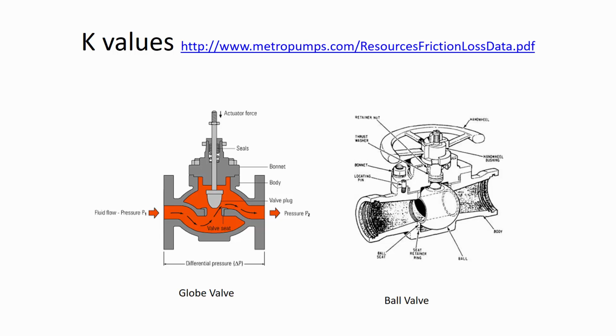The effective diameter of where the water can squeeze through is going to be less than the opening of the hole, and that's why we'd see a K value of 10 for a globe valve, because it's changing directions a couple times, and the opening inside the valve is relatively small compared to the opening on the inlet and the outlet. Whereas a ball valve can just have a quarter turn, so it's really convenient. The water flows through there, but they often will have a center post going through the center, just to maintain the structural rigidity of that ball.